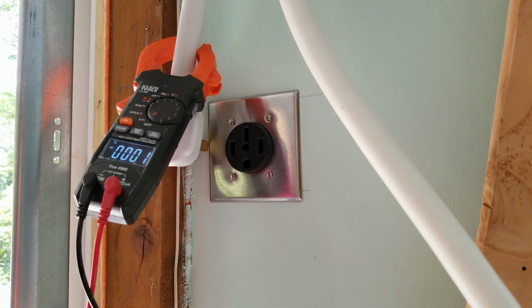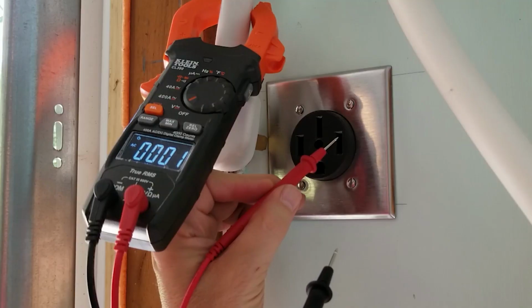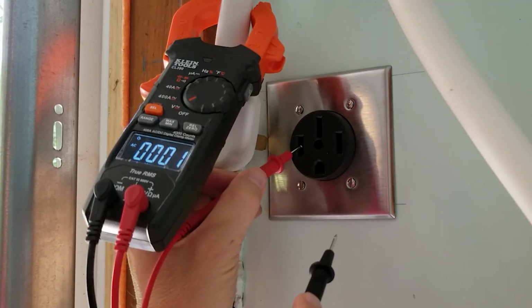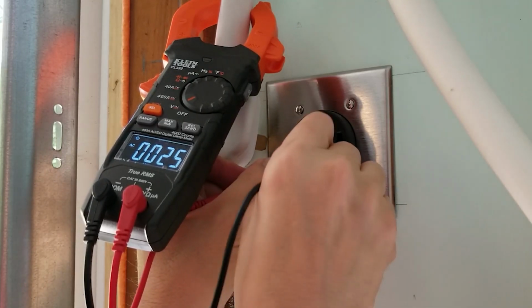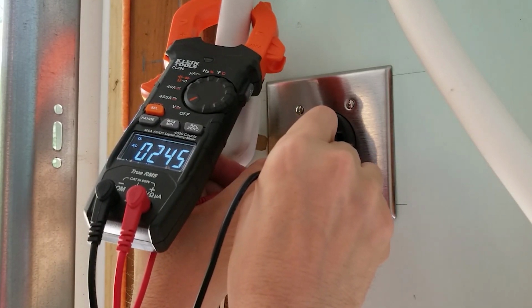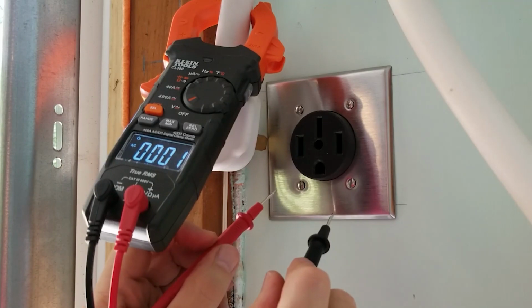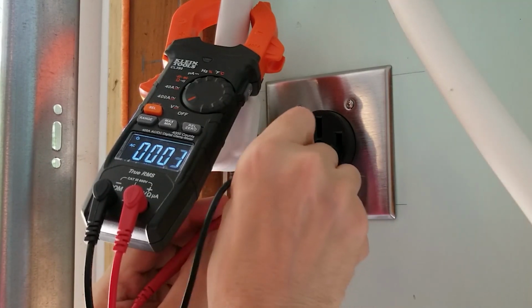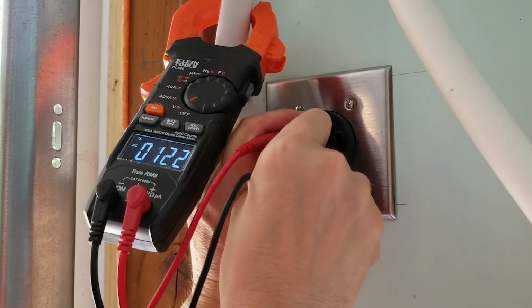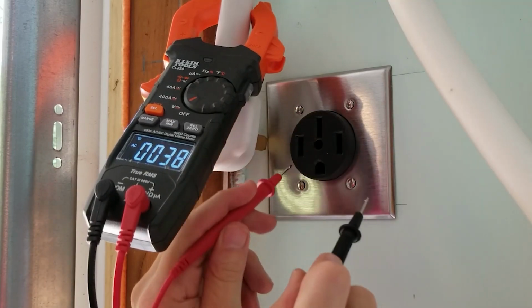With the circuit energized, we're going to take some measurements. These are our two hots, left and right, so that should come up to 240. We get 245, so that's good. Now, if we go from one hot to the neutral, we get 122.